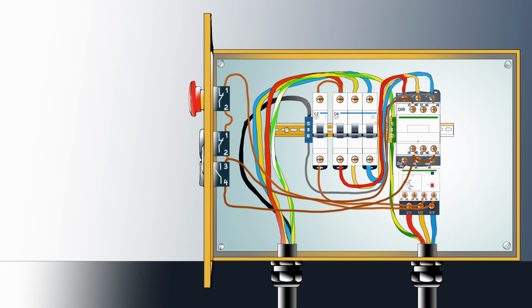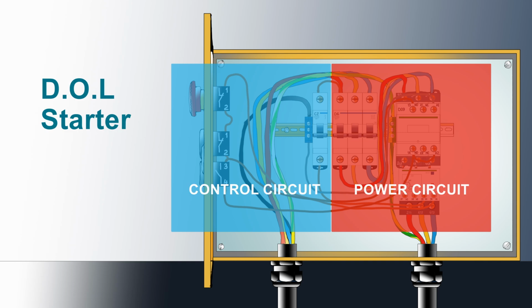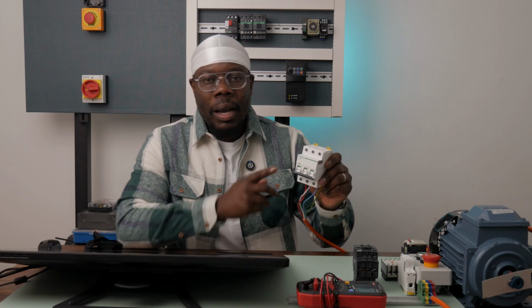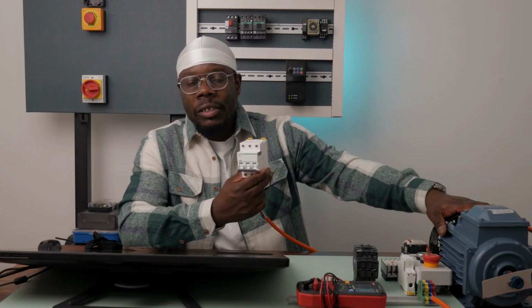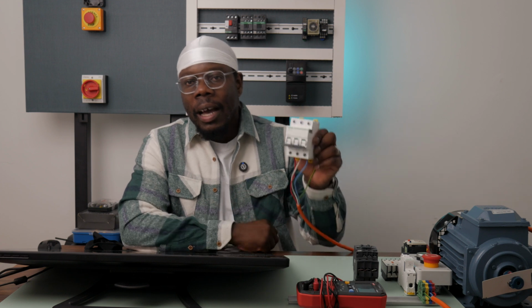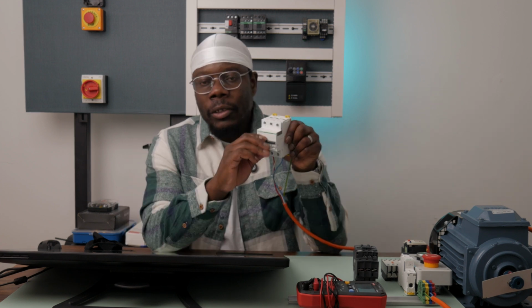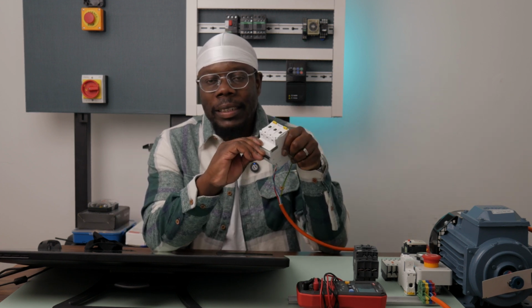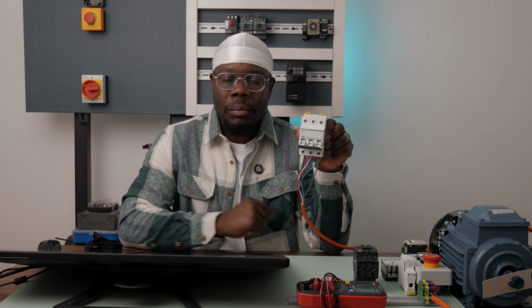Now let's take a look at the components that make up a non-reversing direct online motor starter. A direct online motor starter comprises a low power circuit called the control circuit and a high power circuit called the power circuit. Now imagine hooking this electric motor directly to a circuit breaker like this and using this circuit breaker for starting and stopping this electric motor.